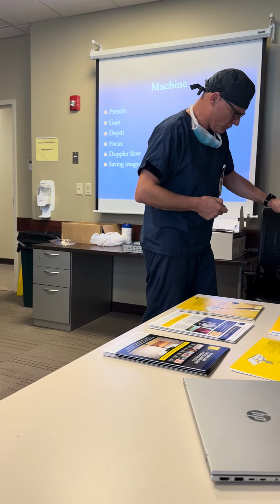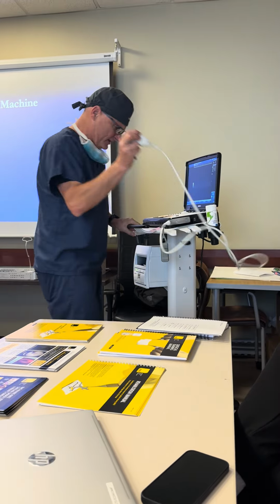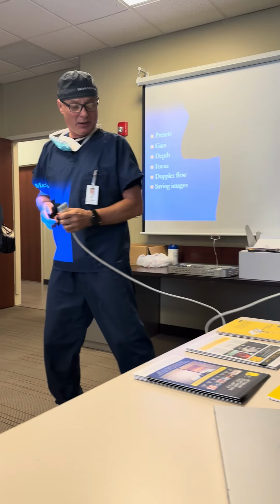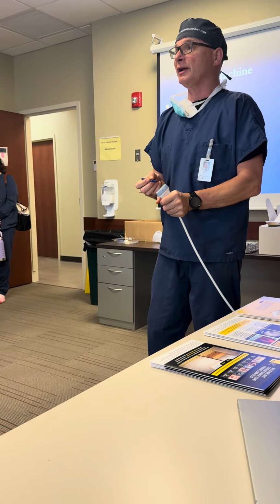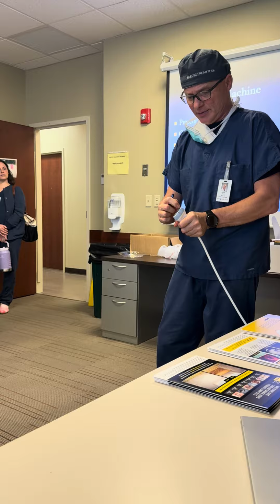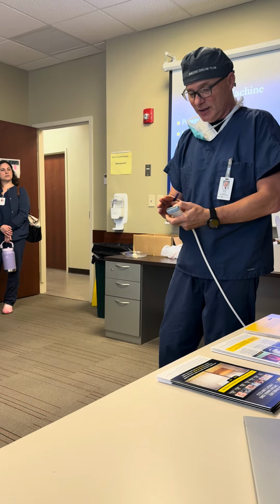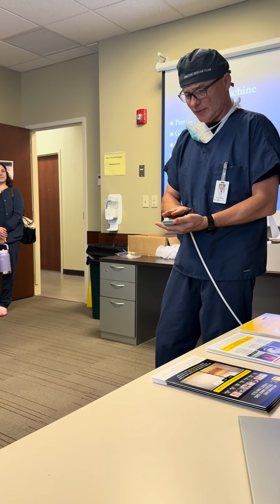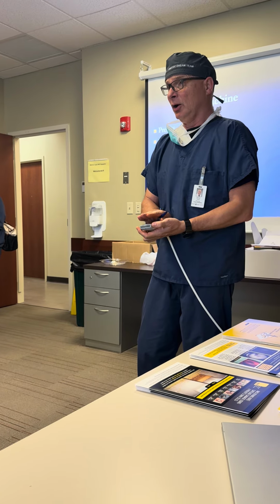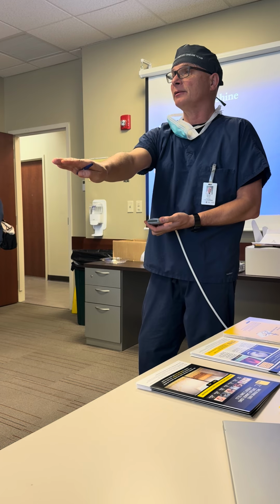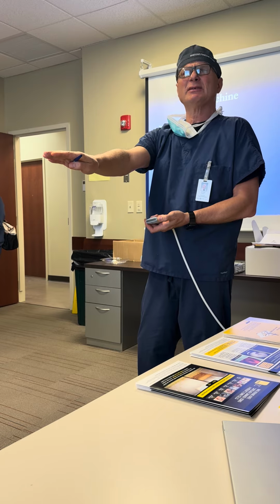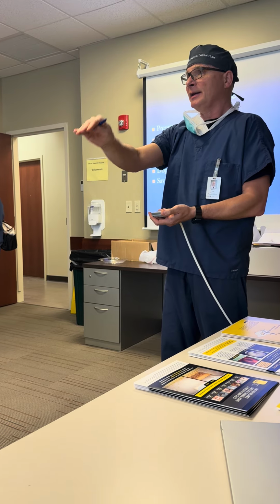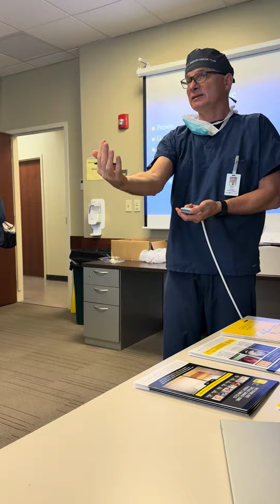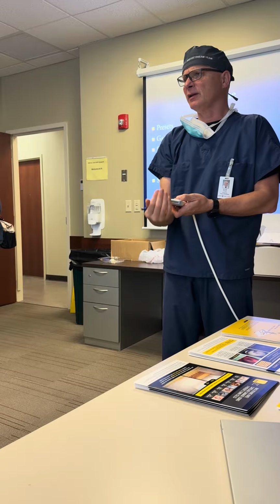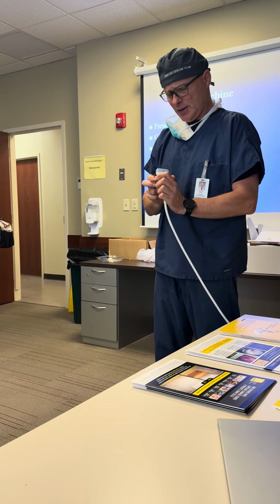The probe that we use is a 6 centimeter probe. It's called a linear probe. This one here. There are like a couple of hundred pairs of crystals lined up in a straight line like this. Each and every one of those crystals, they shoot out ultrasonic energy right straight down, a couple of hundred times per second, and then they shut down and they wait for the signal to return. And from the returning signal, they generate the image, right?